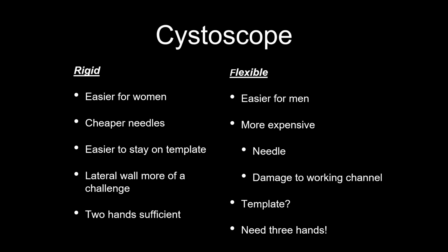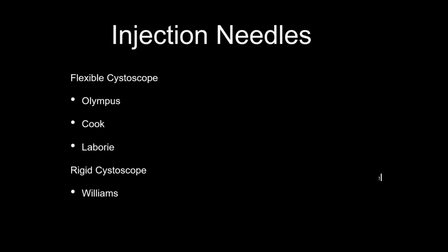You have to make sure that you protect your working channel, depending upon the needle, how you do that. One of the things that I came to learn is, I would have the needle deployed, and I take the needle out without retracting it after I finish with the scope, and you can damage the working channel just pulling the needle out. So always protect that, but you do need a third hand to help you with that.